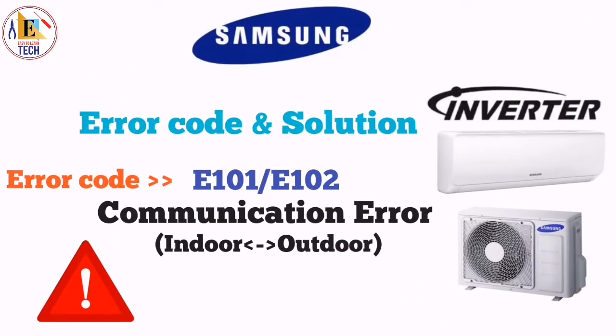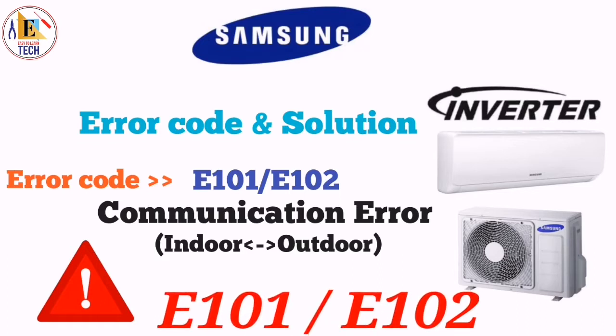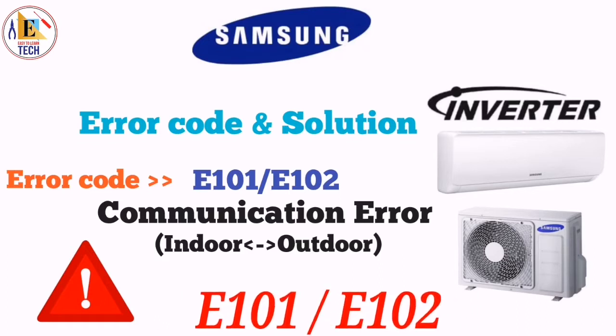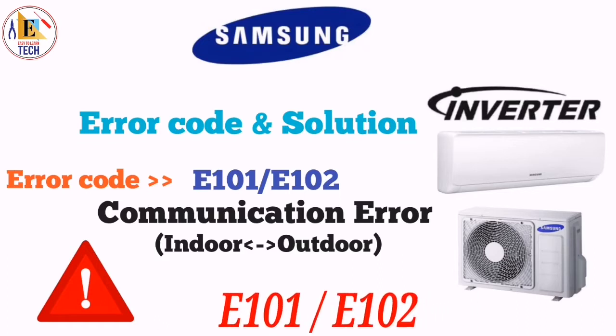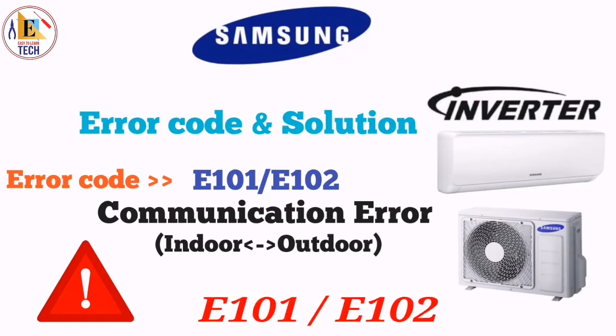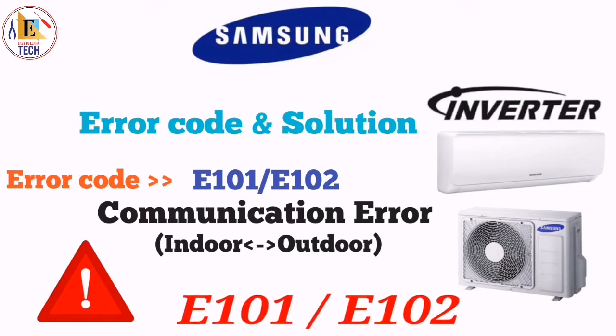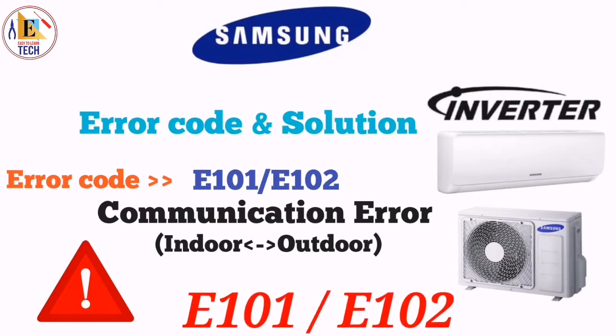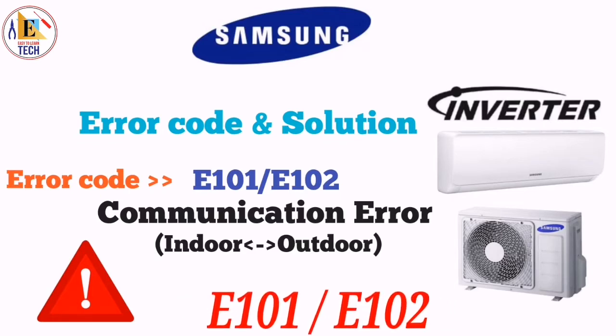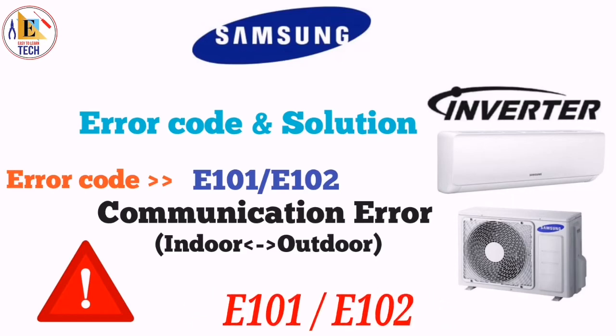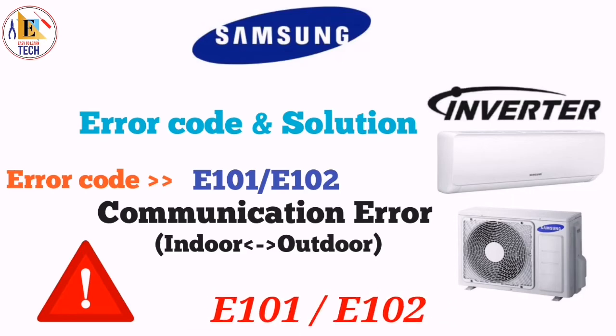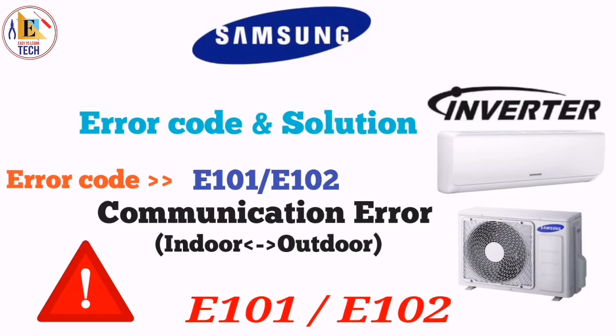When you get the error E101 or E102, it means it's a communication error between indoor and outdoor. If your indoor unit has 3 LED display, at that time LED 1 will be blinking and LED 2 and LED 3 will be on. It means it's a communication error. First of all, you have to check the communication cable between indoor and outdoor. First of all, you have to connect both the cables properly.